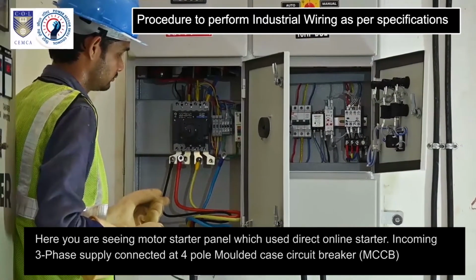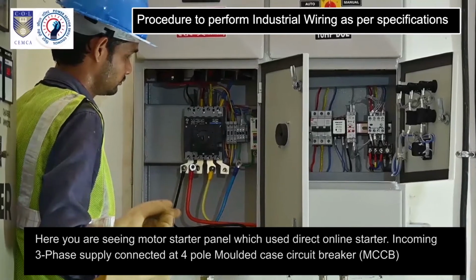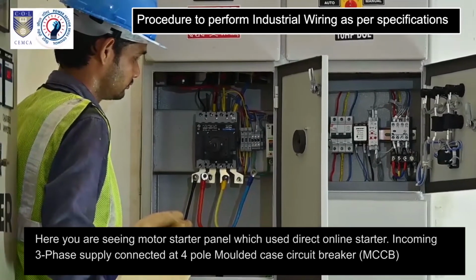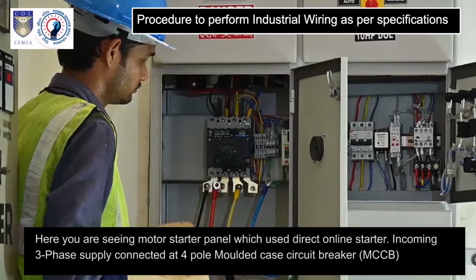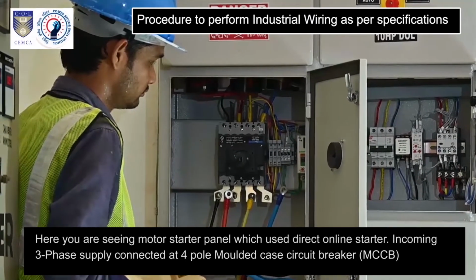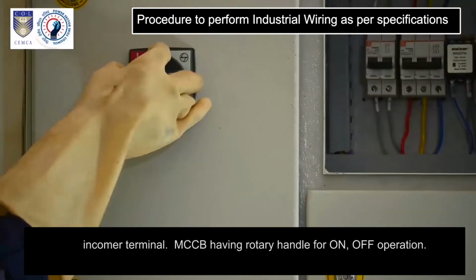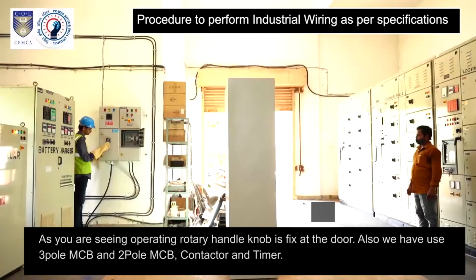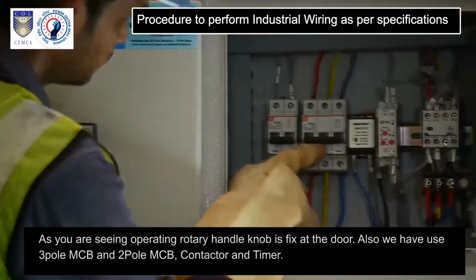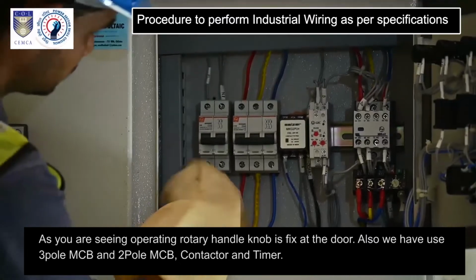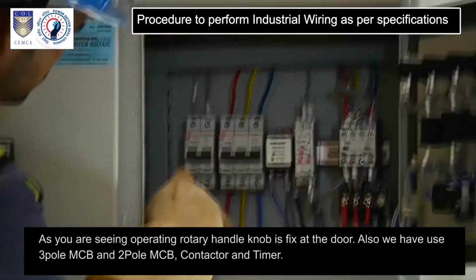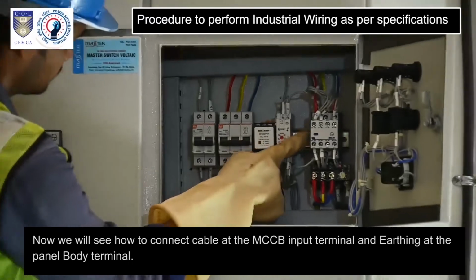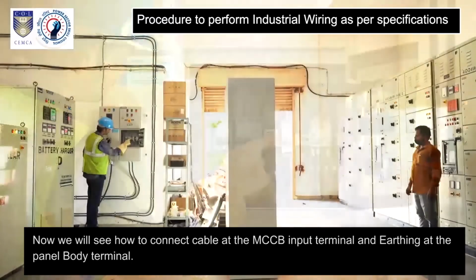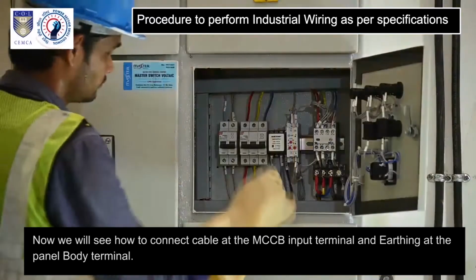Here you are seeing motor starter panel, which uses direct online starter. Incoming three-phase supply is connected at 4-pole molded case circuit breaker, MCCB incomer terminal. MCCB has a rotary handle for on-off operation. As you are seeing, the operating rotary handle knob is fixed at the door. Also we have used 3-pole MCB and 2-pole MCB, contactor and timer. Now we will see how to connect cable at the MCCB input terminal and earthing at the panel body terminal.